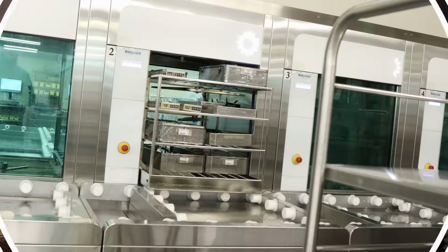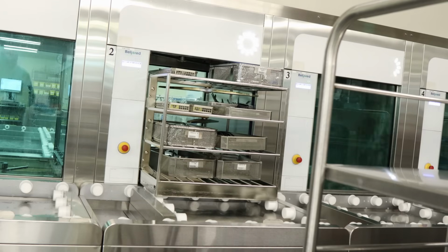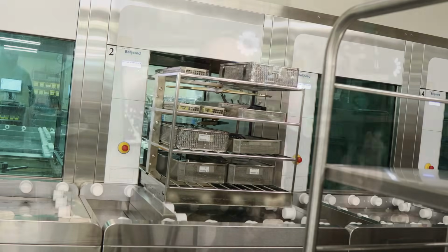Now, back to the automated disinfection machines. They are designed to be a pass-through operation as well, meaning they are almost always part of the wall infrastructure that separates the sides of the department from dirty to clean. These machines are designed so that when one side of the machine is open, the other side is closed. Unless maybe a repair technician is working on them, it'll always work that way. This allows instruments to travel in that infection prevention flow while keeping a solid separation of areas.